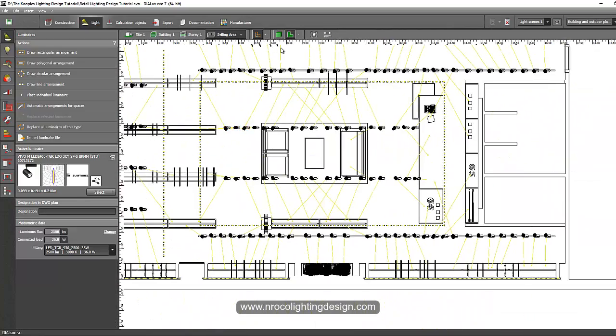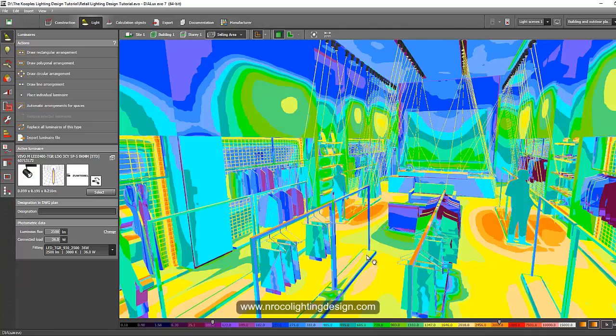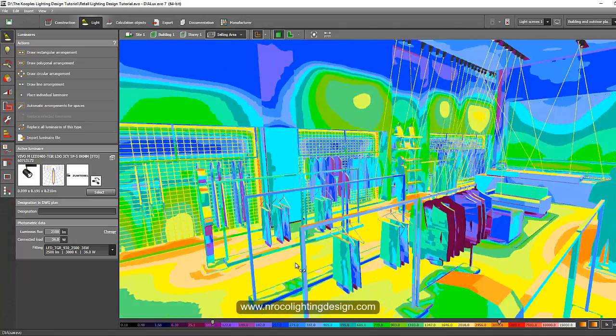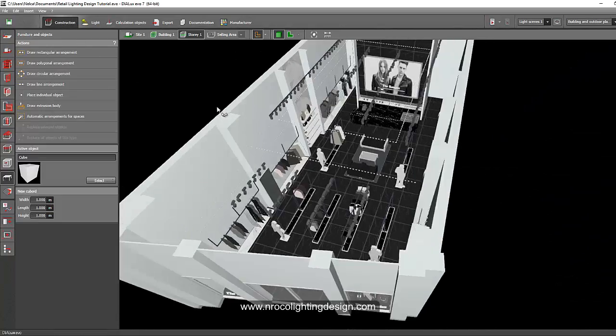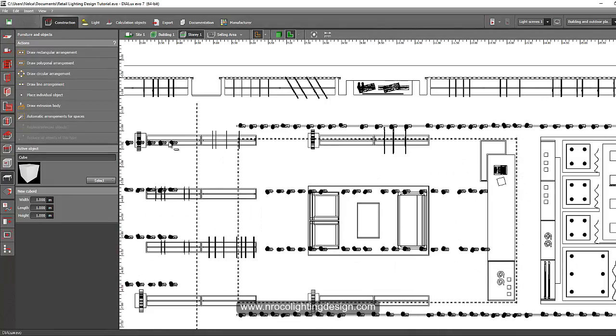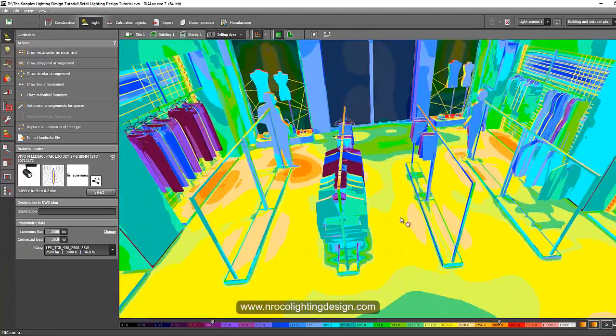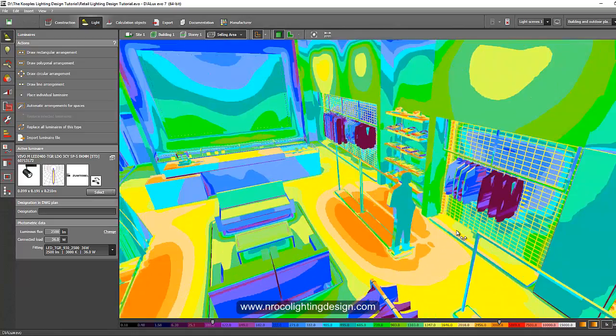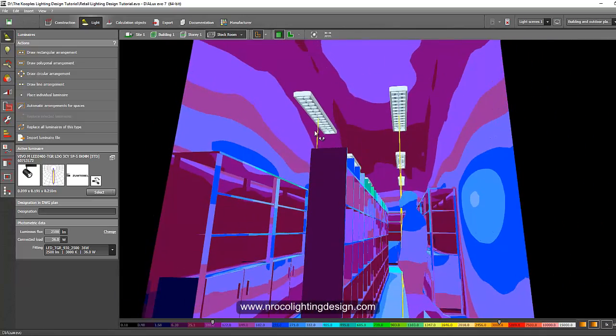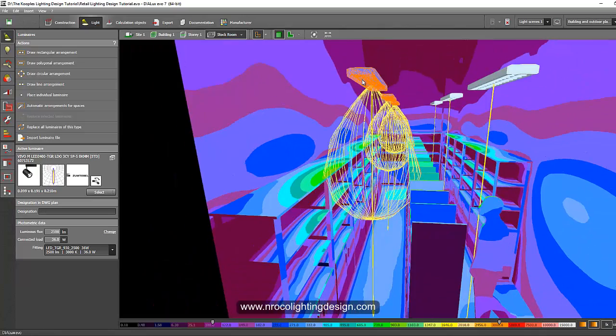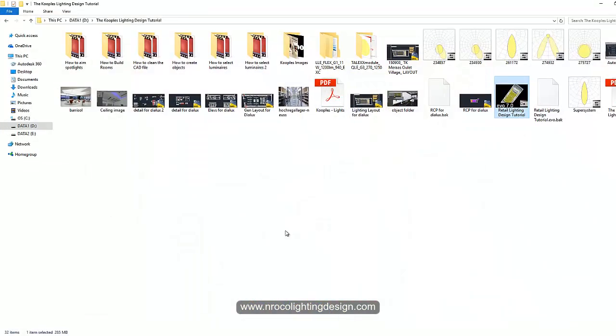I'm going to edit this retail shop again. What I did was copy this file so I have one as a reference and one to edit. I also changed the luminaires in the fitting room to a regular louver fitting, but it doesn't look good — I selected a narrow beam and it still doesn't look right. Let's check the previous design.